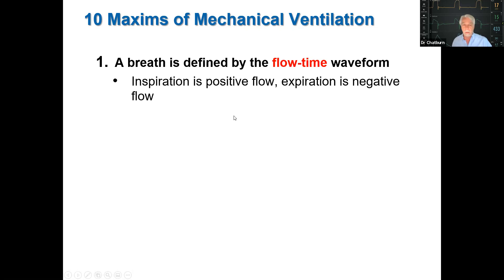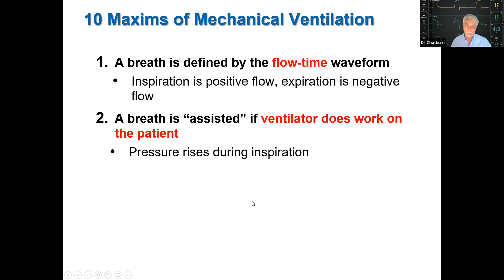The very first concept is that a ventilator is designed to deliver breaths. So we have to define a breath in terms of the way the ventilator thinks of it. We define a breath in terms of the flow and time waveform: inspiration is positive flow and expiration is negative flow. If there's an inspiratory hold — a period of no flow — we lump that in with inspiration, as most ventilator manufacturers do.